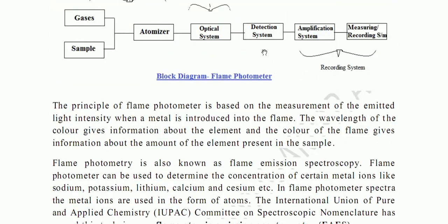The principle of flame photometry is based on the measurement of emitted light intensity when a metal is introduced into the flame. The wavelength of the color gives information about the element, and the intensity of the color of the flame gives information about the amount of the element present in the sample.